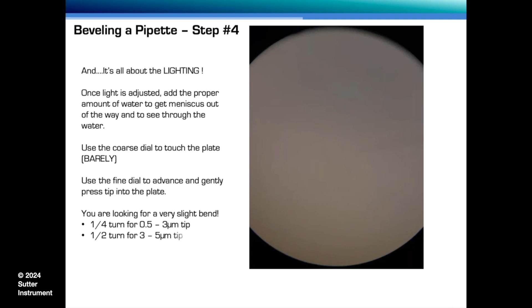And then you'll use the fine dial to gently touch the plate and then advance the tip downward so you can bevel the pipette. And you're going to look for a very slight bend or bow of the pipette, very slight. A quarter turn usually gives you 0.5 to 3 microns if your pipette has not been trimmed or cut back. Half a turn gives you a 3 to 5 micron tip. 3/4 of a turn is good for a 7 to 10 micron tip, but sometimes you might need to trim it first.